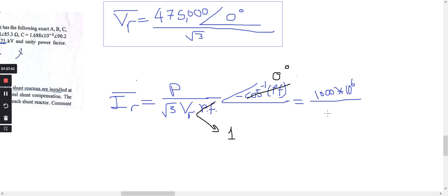So square root of 3 times the receiving end voltage, which as a line value is 475,000, gives VR as a phasor equal to a real number with angle 0. 1000 times 10 to the 6 divided by square root of 3 times 475,000 is 1215.474 amps.